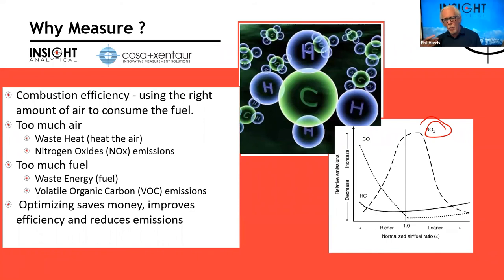At the same time, if we don't put in enough air, if we have too much fuel for the amount of air there, if we run the burner rich on fuel, what happens is we don't burn all that fuel. So now we have higher volatile organic carbon emissions and we waste some energy. We've left some energy in that unburned fuel. So trying to hit that sweet spot where we can reduce the amount of unburned fuel, stay on the right side of that NOx curve, reduce CO emissions, all of that optimization saves us money on fuel. It improves the efficiency of our burn and it reduces environmental emissions.